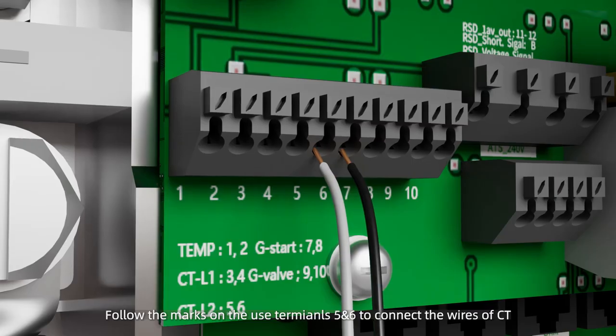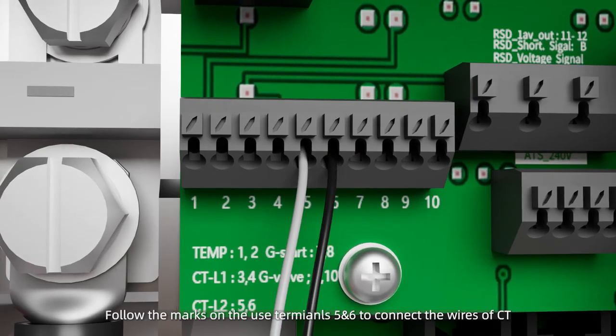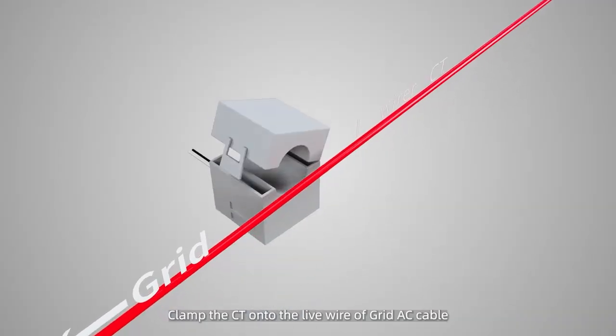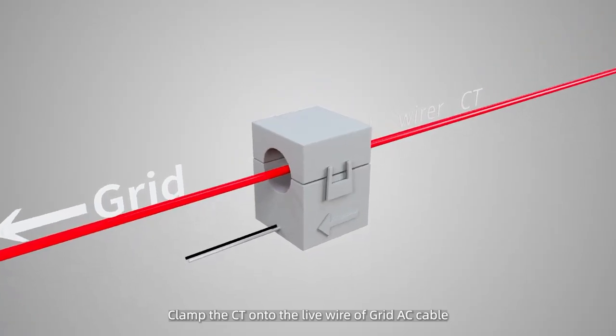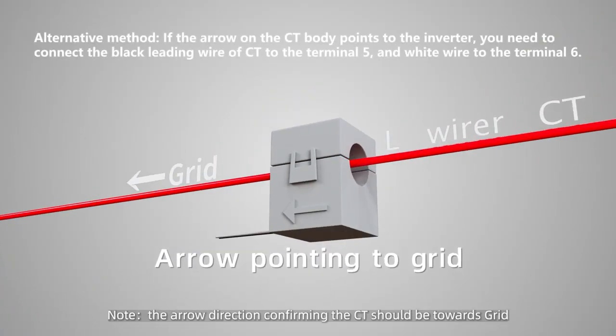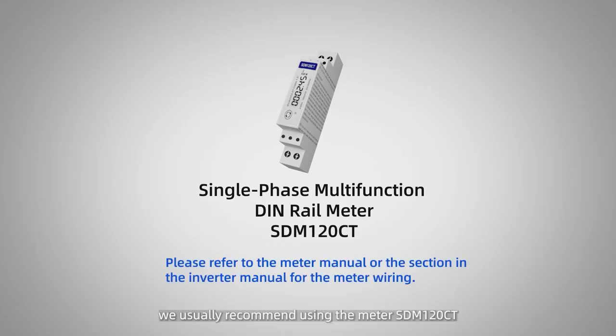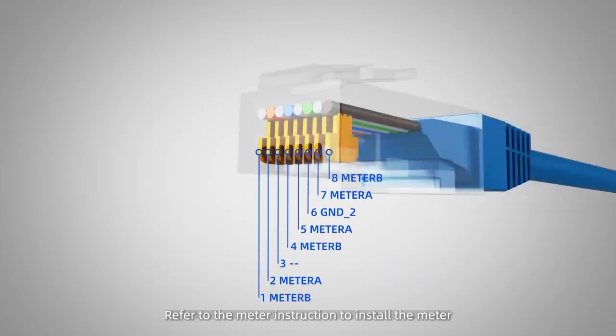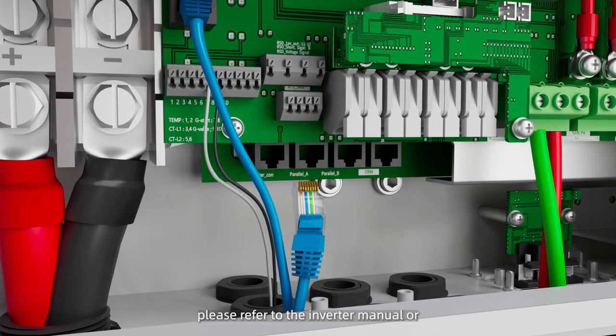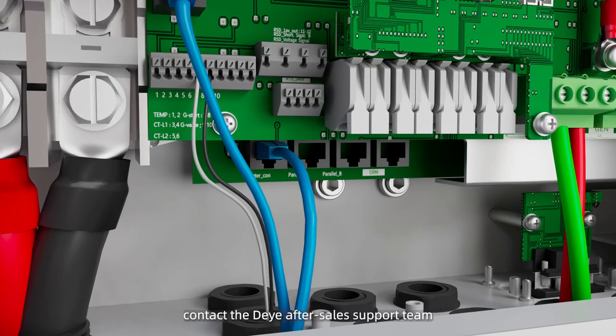CT connection. Follow the marks on the PCB board to use terminals 5 and 6 to connect the wires of the CT. Clamp the CT onto the live wire of grid AC cable. Note, the arrow direction confirming the CT should be towards grid. Meter connection. In Australia, we usually recommend using the meter SDM120 CT. Refer to the meter instruction to install the meter. When connecting the meter CT, the CT always faces towards the inverter. For other types of meters, please refer to the inverter manual or contact the Deye after-sales support team. Connect the RS485 port of the electricity meter to the meter port of the inverter.